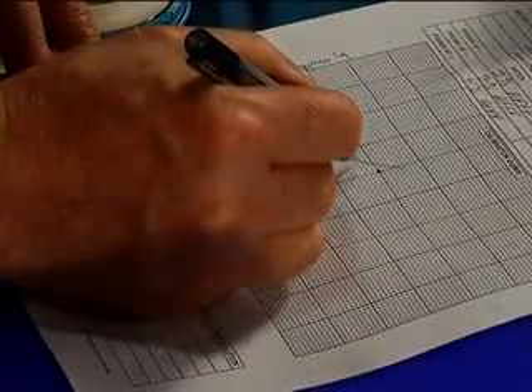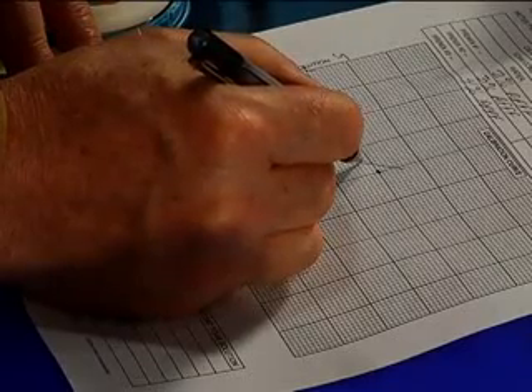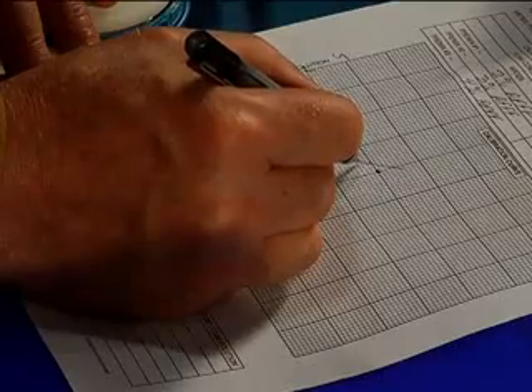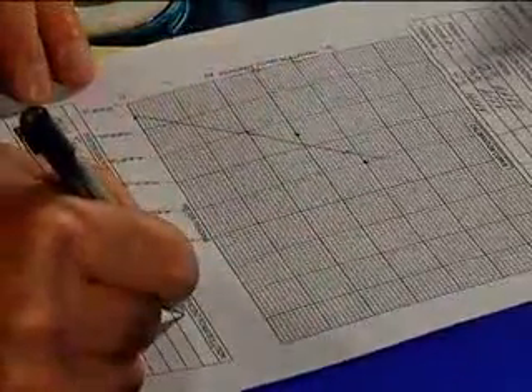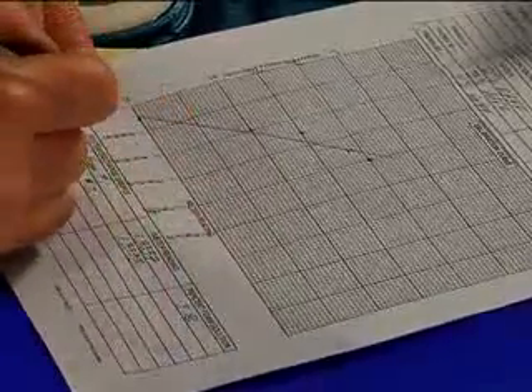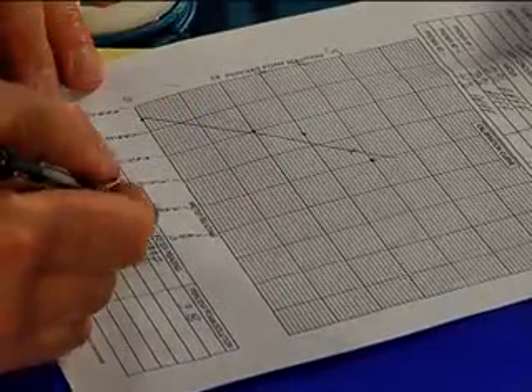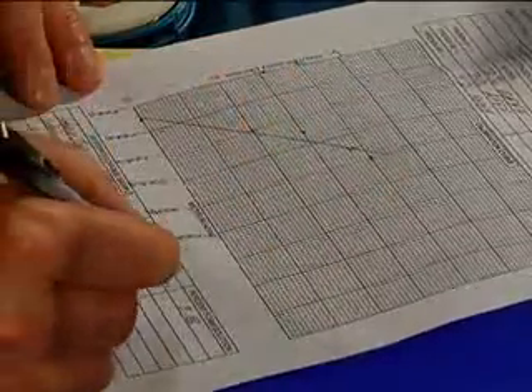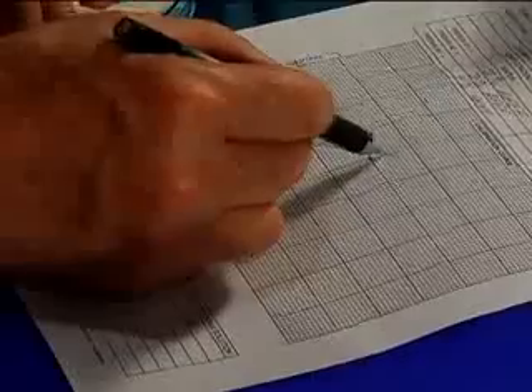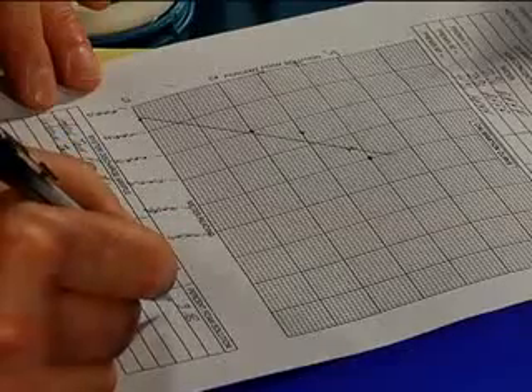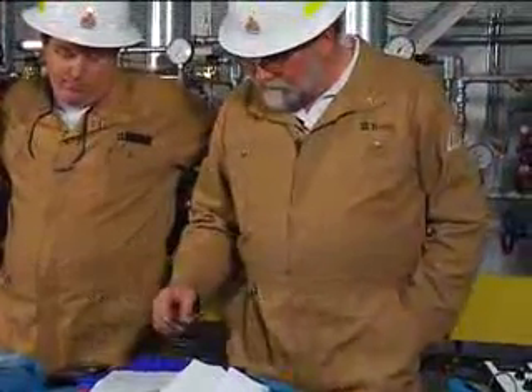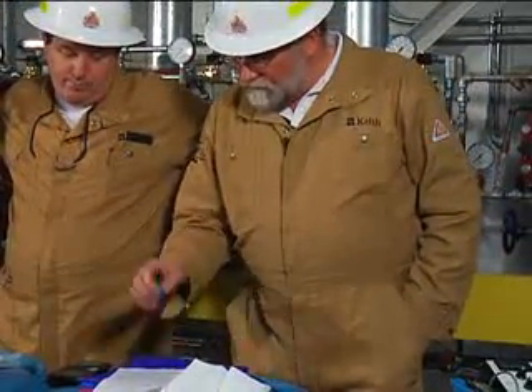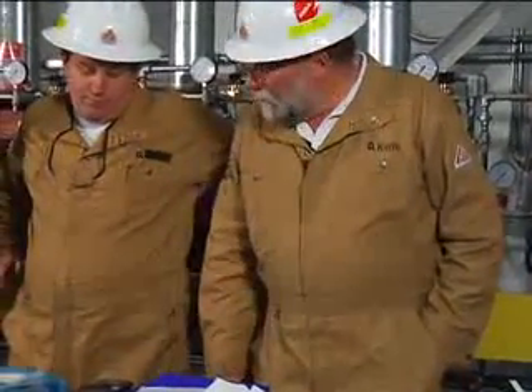Our sample that read 1.3337, which is this point right here, was reading about 3.8%. Our sample that was reading 1.3340, I'm going to call that 4% because it actually fell right on the reading, but if I read it off the chart, it'd be reading about 4.3, but I'm a little suspicious about that point. I'll write down 4.3%. So our concentration percentage on the first system that we tested with Flomax proportioning foam concentrate was on average about 4%.